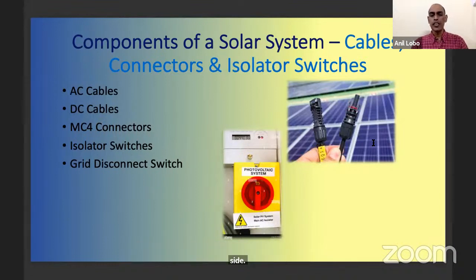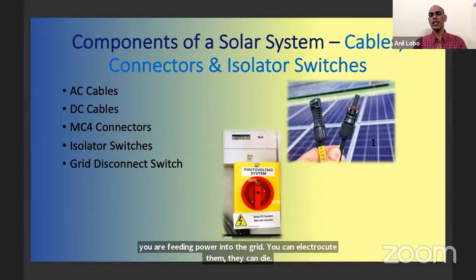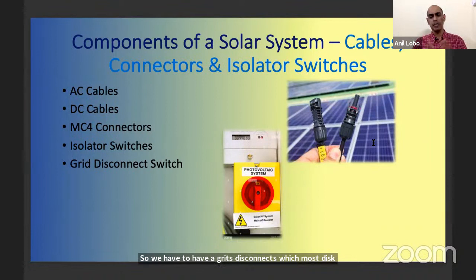Very important is a grid disconnect switch - this is an often forgotten switch. Remember, if your grid has failed and service technicians, the electricity grid technicians, are working on the grid while you're feeding power into it, you can electrocute them - they can die. So we have to have a grid disconnect switch. Most discoms, the electricity boards, demand that your solar inverter, if connected to the grid, has an auto disconnect switch. Before installation, they will come test, verify, and certify before they sign a power purchase agreement with you.